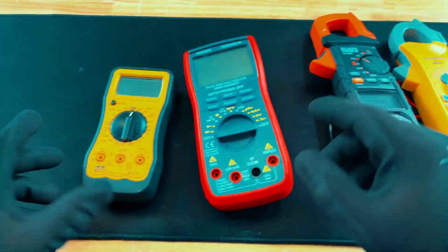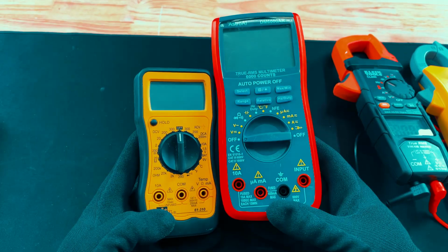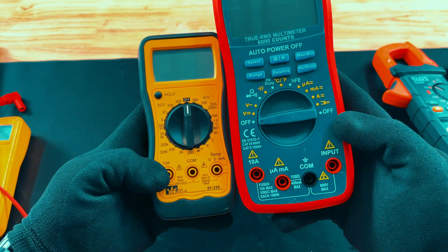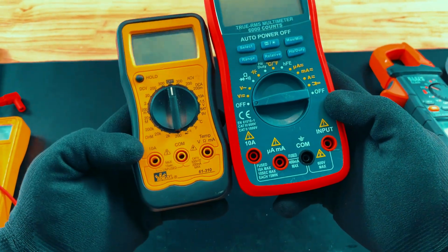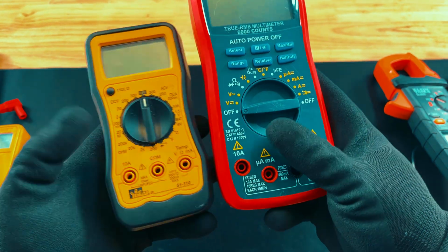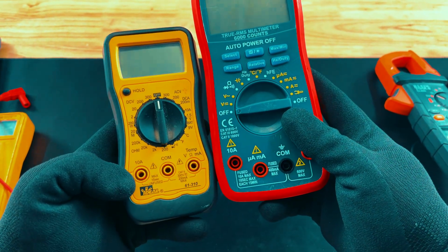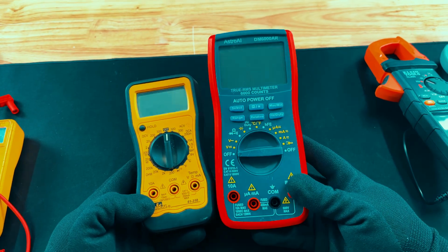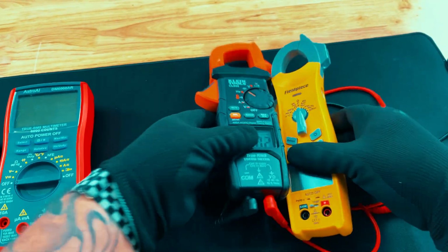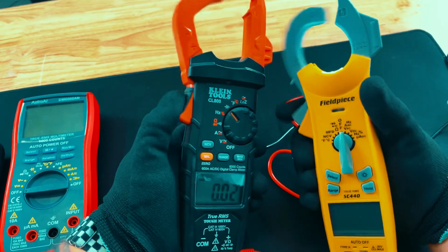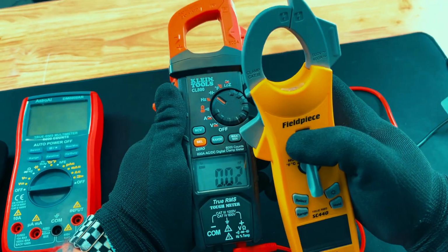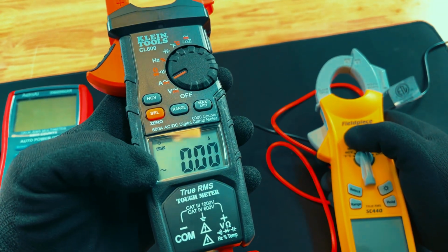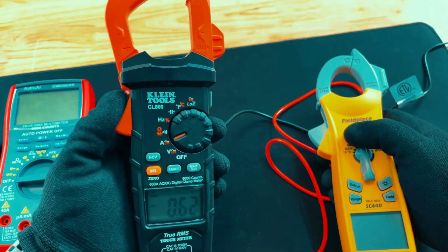But in certain situations where you have meters like these, they have other options. Some of these meters will have the 10 amp fuse, and that's for measuring larger currents. Anything larger than 200 milliamps, you want to switch over to the 10 amp. Of course, these are not amp clamps, so you're going to have to use the leads, and that's why they give you that option. You're not going to have that with these. These have clamps. You just switch to amps. As you can see here, I'm going to switch over to amps. Alternating current, AC voltage. You see the line there. At that point, I can check amp draw.